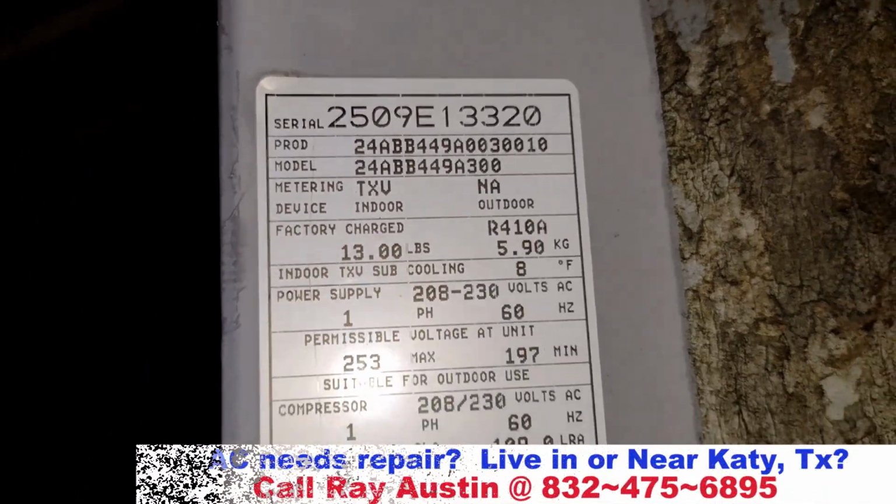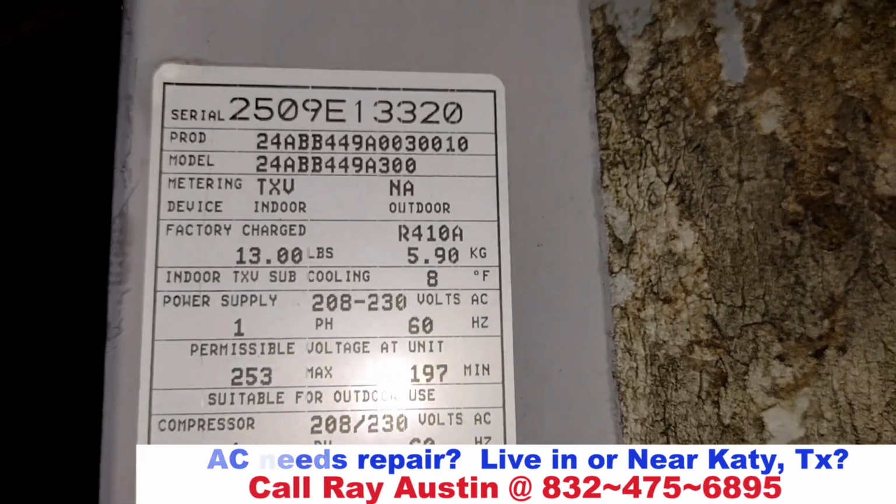So for this customer, nearly 4 years pass before I go back out to this house. Now, if you subscribe to my YouTube channel, you'll see that this doesn't always happen. So this customer's condenser fan motor had failed, and you'll see that it wasn't typically what I see because this unit was tripping the breaker. Initially I thought it was the compressor, but I went the additional step and tested it to make sure. Here I'm showing that I'm replacing that fan motor because it had shorted to ground.